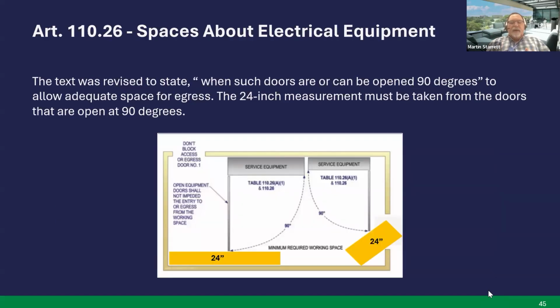Space about electrical equipment. The text was revised to state when such doors are or can be opened 90 degrees to allow adequate space for egress. The 24-inch measurement must be taken from the doors opened at 90 degrees. So for any electrical equipment that falls under this article, the egress would be with the doors completely open at 90 degrees. You have to have at least that 24-inch egress width. Next slide.